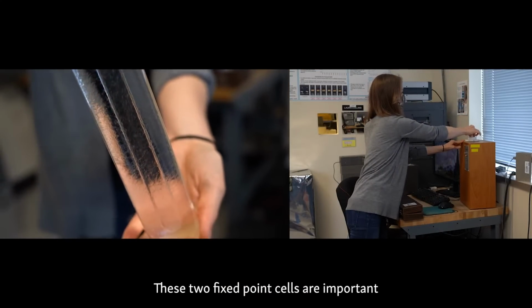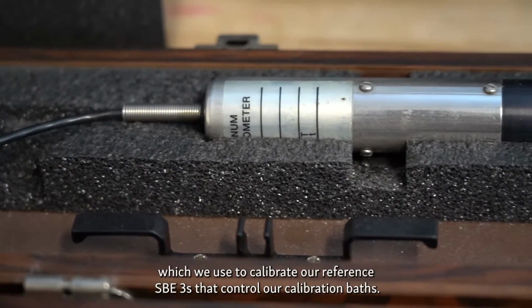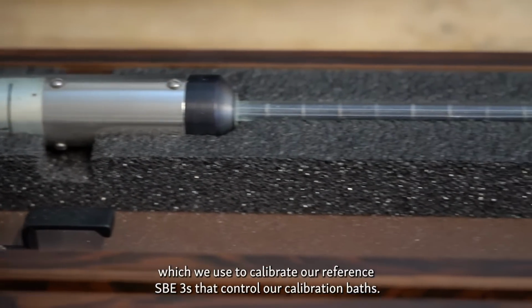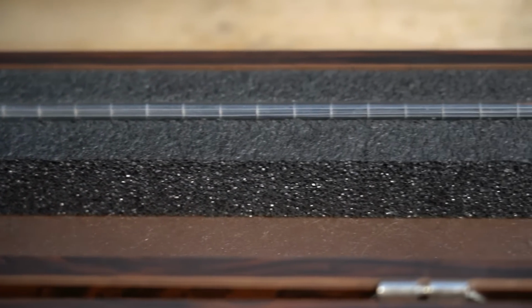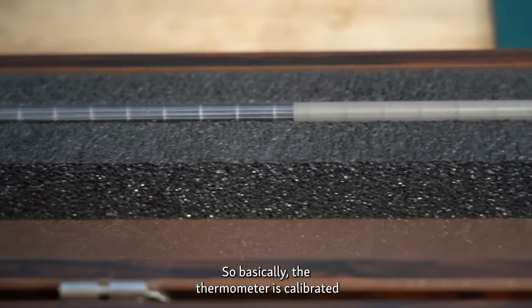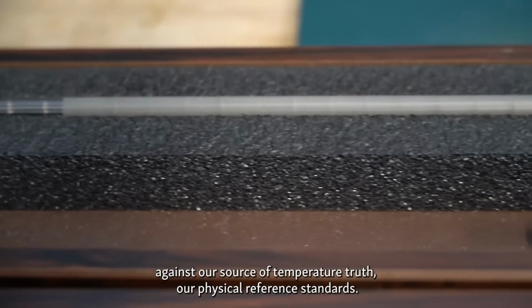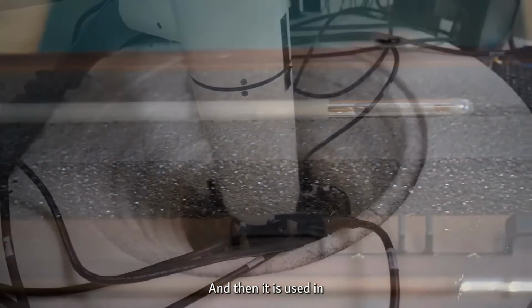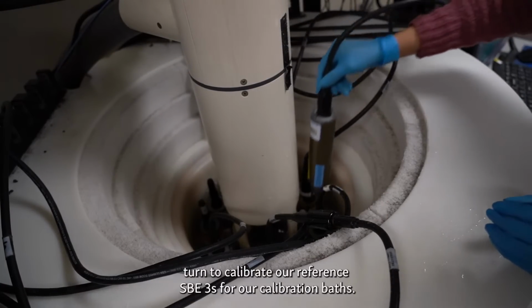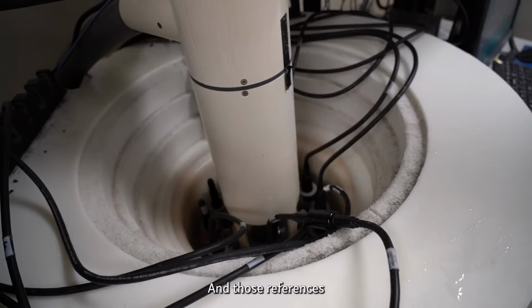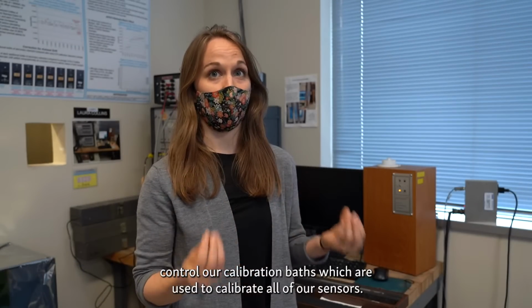These two fixed point cells are important because they allow us to maintain a platinum reference thermometer, which we use to calibrate our reference SBE 3s that control our calibration baths. So basically the thermometer is calibrated against our source of temperature truth, our physical reference standards, and then it is used in turn to calibrate our reference SBE 3s in a calibration bath. And those references that control our calibration baths are used to calibrate all of our sensors.